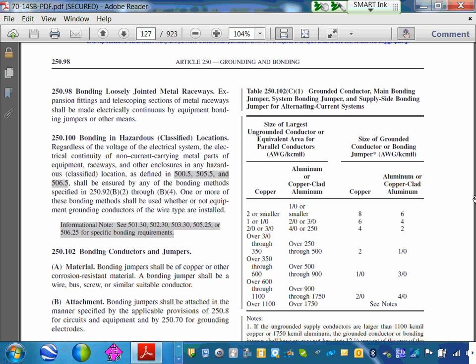Okay, this table, highlight this table. Please highlight this table. You use this table to size the following. Can you guys see the word grounded conductor here? That's a fancy name for what? Neutral. So you size at the service. This is only at the service. Okay. Number two. This is number one. Number two. Can you guys see the main bonding jumper here? This is the one highlighted, main bonding jumper. That's number two. Do you guys remember the main bonding jumper? We just talked about it. That bonding the neutral to the ground. Okay. Number three. Supply. Can you guys see that? Supply side bonding jumper. Number three.